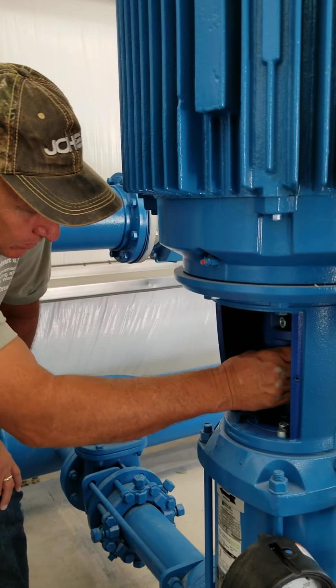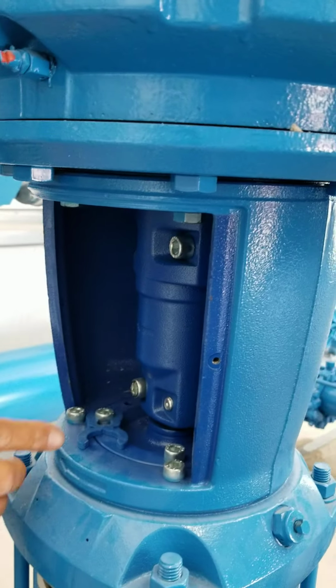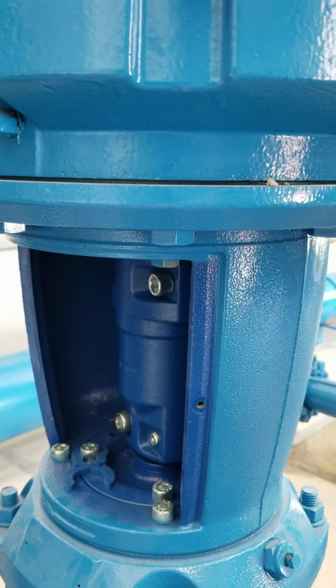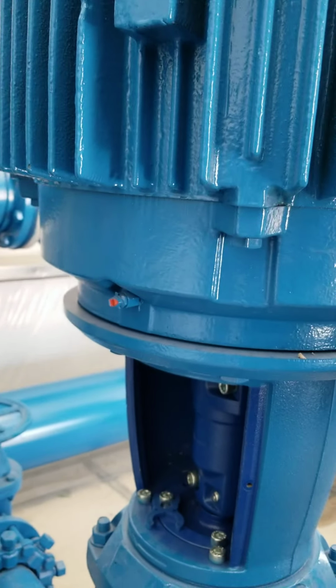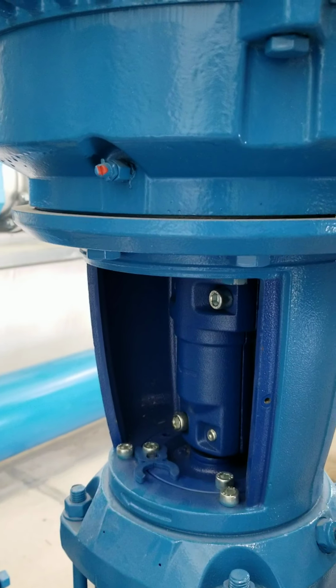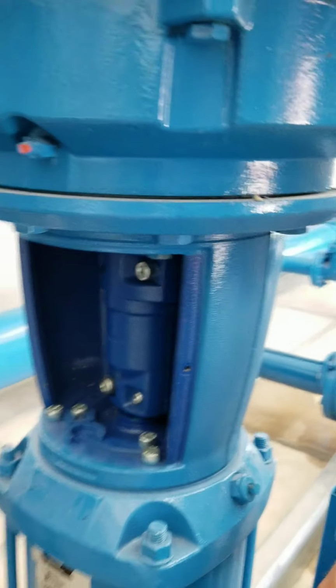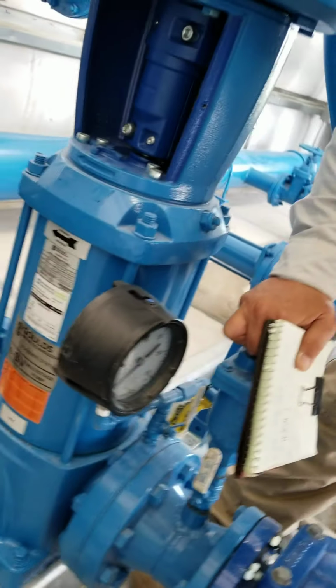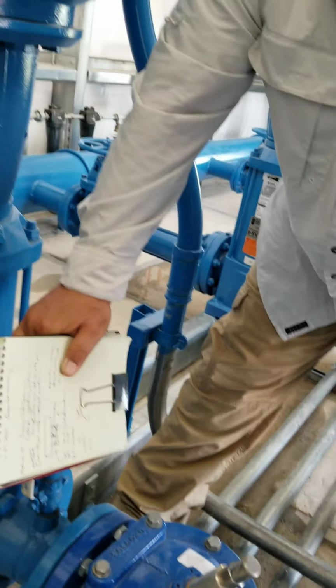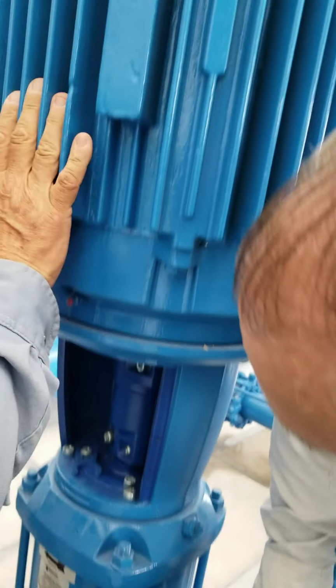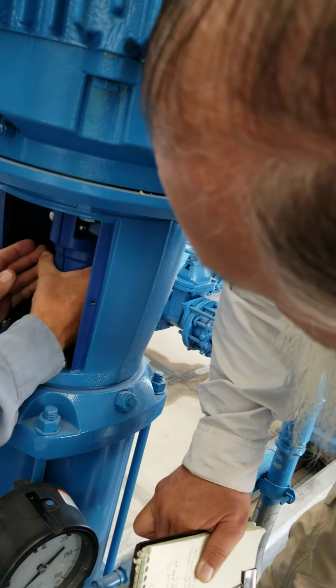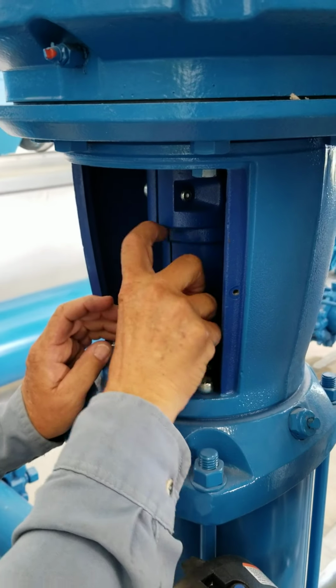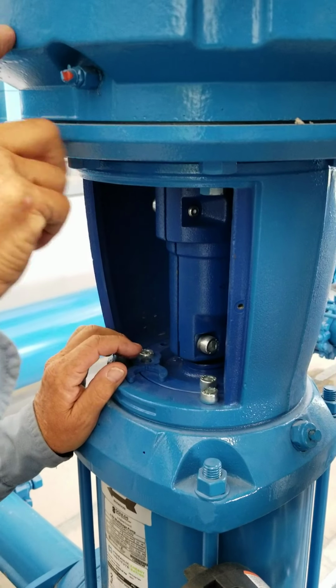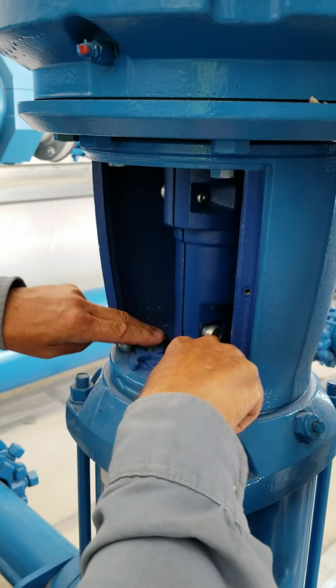Okay, to replace the seal, if you ever get water coming out of here, you'll undo this coupling from the motor, and you'll see that the shafts are about that far apart from each other. Is there any tightening tensioners on that? So what you're going to do is, hey James, can you tell him how to replace the seal? With these big motors, let me turn it off. You're going to unbolt this coupling right here, and there should be enough space in here where you don't have to pull the motor. And so you just unbolt these.